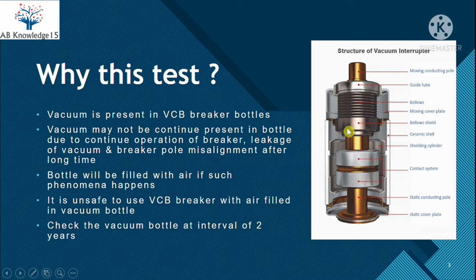If this bottle is filled with air, if the vacuum has leaked out, then it is unsafe to use this vacuum bottle for continued operation. For that purpose, we check this bottle at an interval of 2 years. This interval is increased or decreased as per the operation of the breaker. If your breaker operation is higher, you can decrease this time, and if your breaker operation is somewhat less, then you can increase this time.